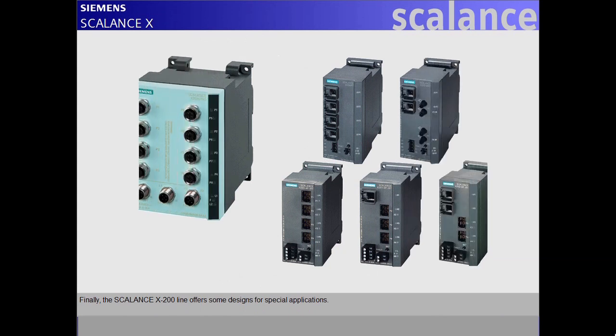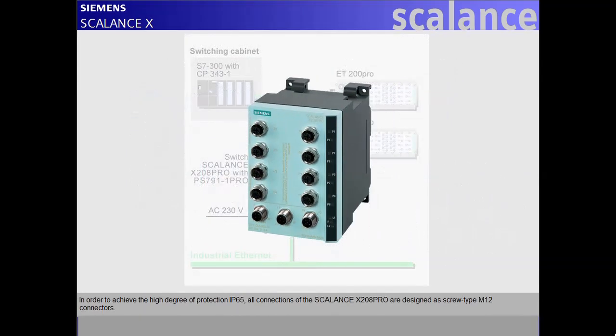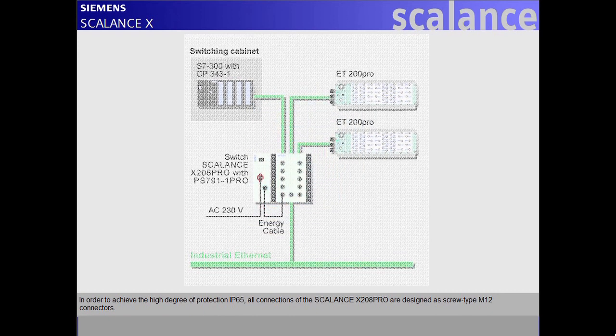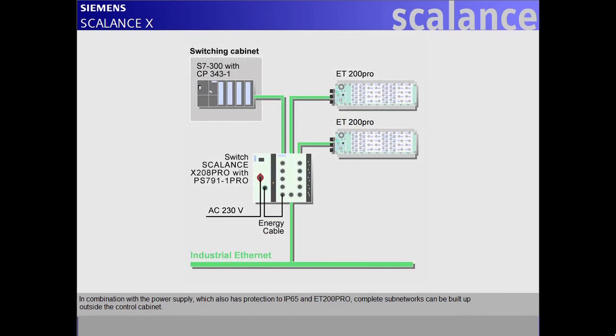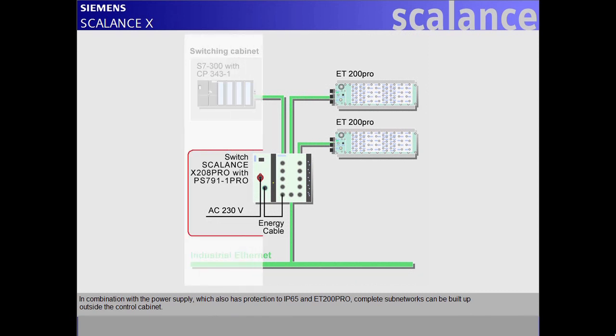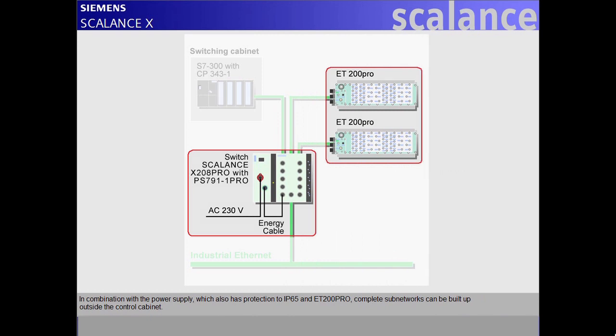Finally, the Scalance X200 line offers some designs for special applications. In order to achieve the high degree of protection IP65, all connections of the Scalance X208 Pro are designed as screw-type M12 connectors. In combination with the power supply, which also has protection to IP65 and ET200 Pro, complete sub-networks can be built up outside the control cabinet.